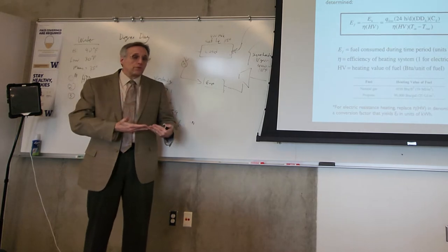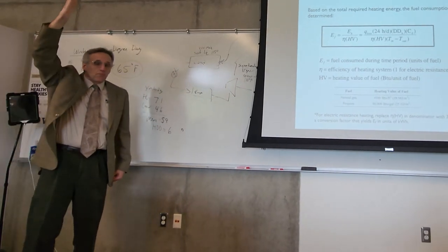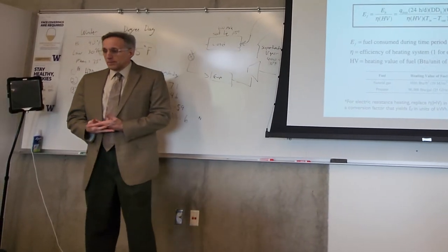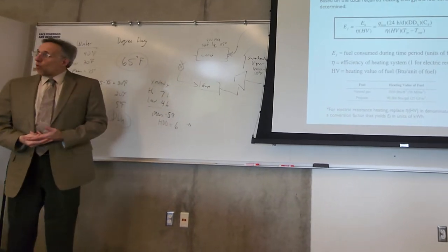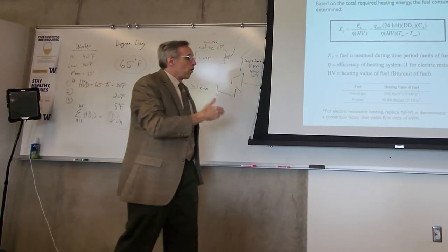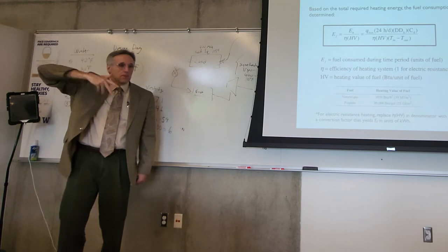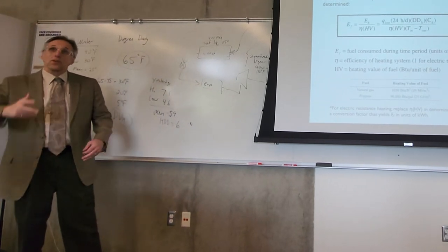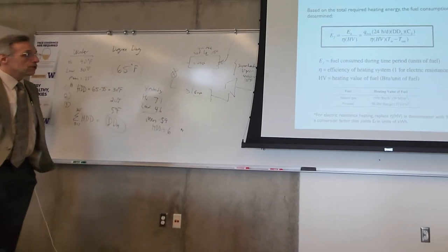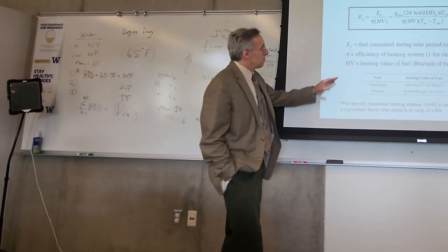And really, when you burn fuel, you're generating thermal energy, and that's easy to do. Again, that's going in nature's direction. It's just some of that energy ends up going off into the environment. It goes up the chimney, right? You're burning fuel, and a considerable amount of energy escapes with water vapor. When water vapor goes up the chimney with the combustion byproducts, that represents lost energy. So modern water heaters and gas furnaces have a little mechanism to condense the water vapor out of the flue gas. And that recaptures that latent energy that otherwise would have been lost going up the chimney. So you can get into the 90s now for modern gas furnaces. But I think older models are going to be in the 70s and more economical, modern ones in the 80s.